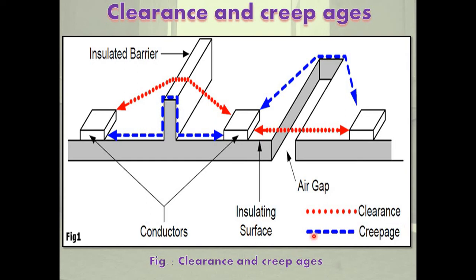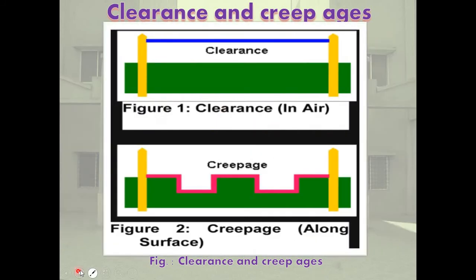For heavily polluted industrial areas, higher creepage distances are recommended. For indoor clean atmosphere, lower creepage distances are recommended. Clearance and creepage are of interest to safety personnel and plant or equipment designers. The size, configuration and three-dimensional layout of the installation are influenced by clearance requirements. The length of insulators and bushings is also influenced by clearance requirements. Thus, the surface profile of solid insulators is dictated by creepage requirements.